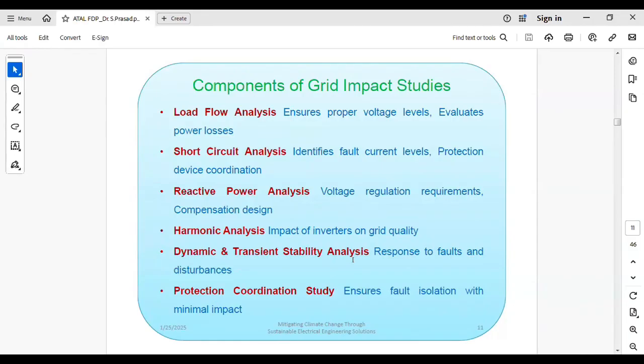And then dynamic and transient stability analysis. Basically, the transient analysis is needed whenever you are going to integrate the PV plant to an existing plant. Suppose the existing plant already has a number of synchronous generators or diesel generators, and you are going to integrate the PV plant to it. Then, because of the integration, at the point of interconnection you have to analyze the transient stability. Because of a fault happening at the PV end, are the generators stable or unstable?